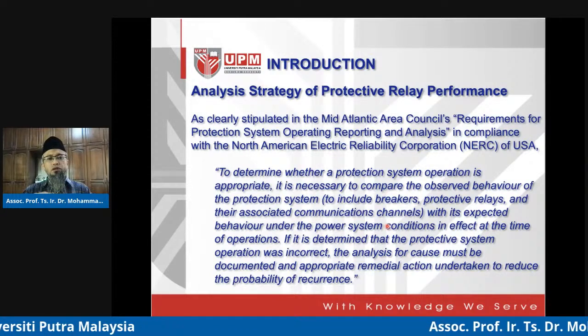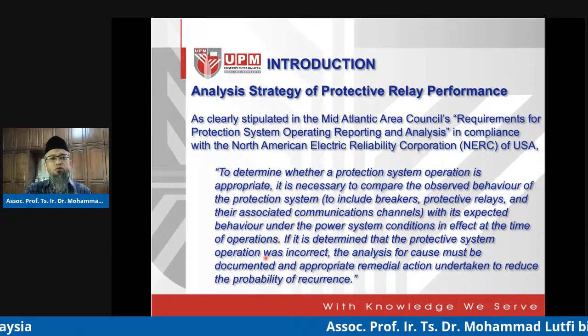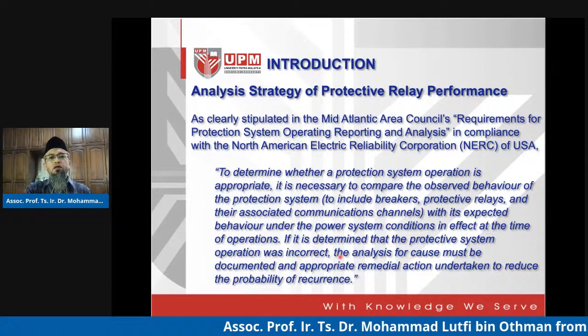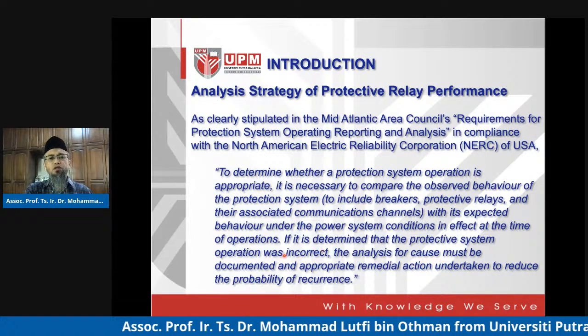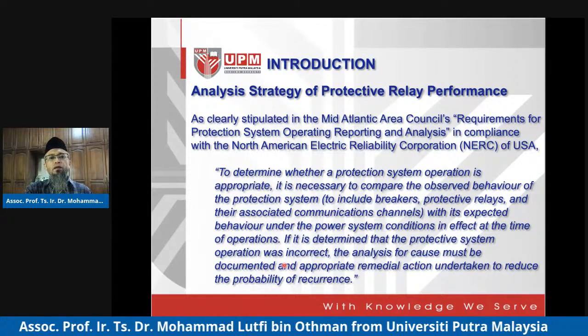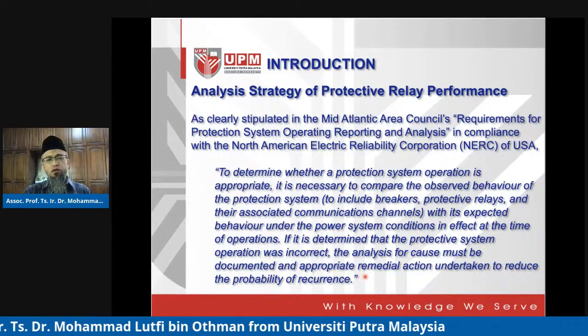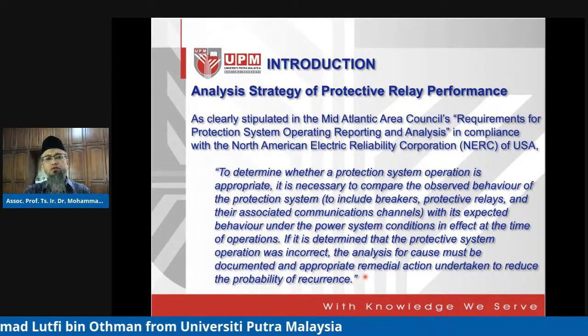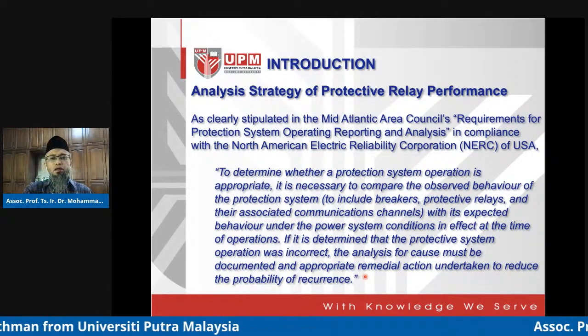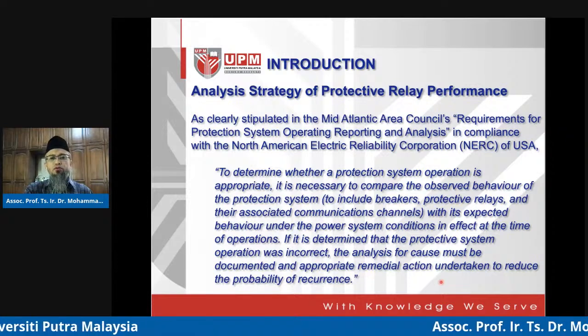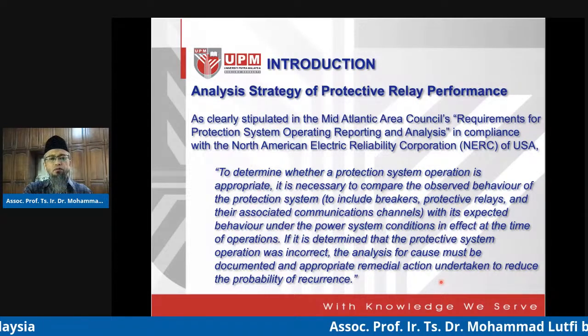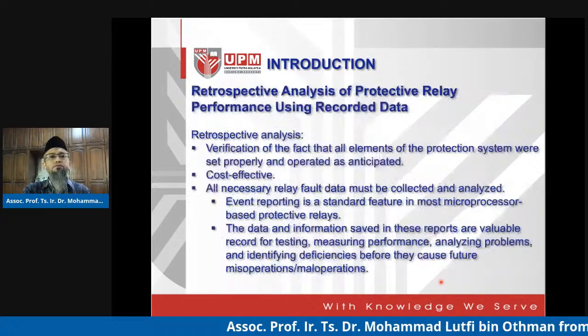If it is determined that the protective system operation was incorrect, then the analysis for cause must be documented and appropriate remedial actions taken, meaning we need to understand the symptoms, deal with the situation, and take remedial actions to address the misoperation or maloperation of the relay.